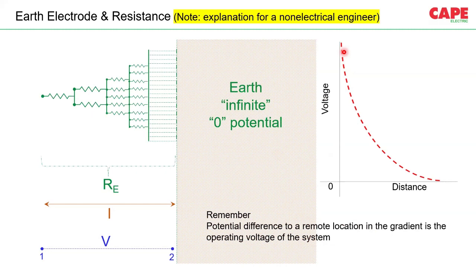I always try to repeat this particular word in several of my presentations because in India, we have a misunderstanding. You can find this misunderstanding in several tenders. Let's say, for example, including some of the metro railway earthing tenders, they say 230 volt application, 50 kiloampere fault current going to earth, and they design an earth electrode, a large mesh, thinking that a large voltage, 15 kV voltage gradient or 15 kV step potential is going to come. That is not correct. The peak of the voltage is the operating voltage.